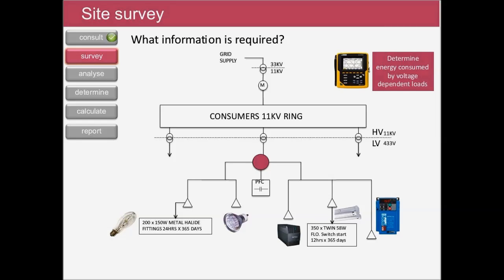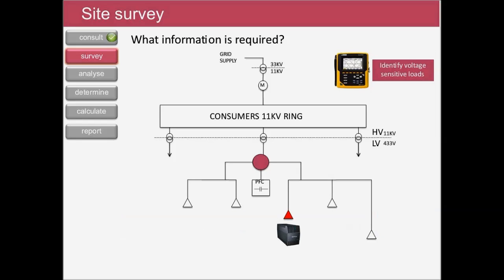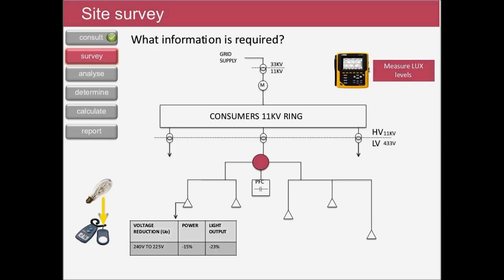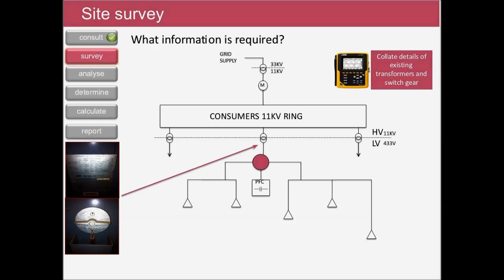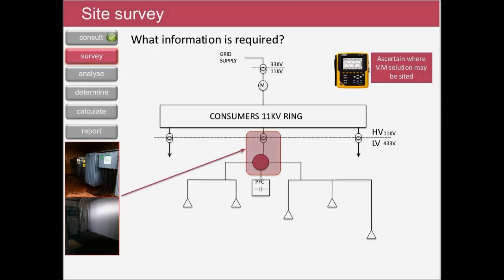Perhaps most importantly, in order to calculate the amount of energy that could be saved through a controlled voltage reduction, the proportion of energy consumed by the site's voltage-dependent loads needs to be ascertained. Voltage-sensitive equipment should be identified and considered in conjunction with site-specific load profiles to ensure that they're still going to operate correctly following the integration of the selected voltage management solution. Lux levels in areas where voltage-dependent lighting is utilised should be checked to ascertain if the reduction in voltage is likely to compromise the minimum acceptable lux levels for the particular area of site. Key information should be gathered from existing transformers and switchgear to ascertain capacity and, of course, potential siting of the appropriate solution.